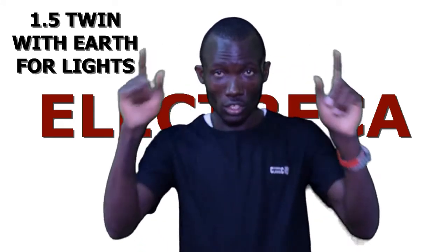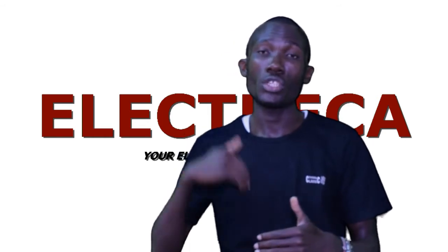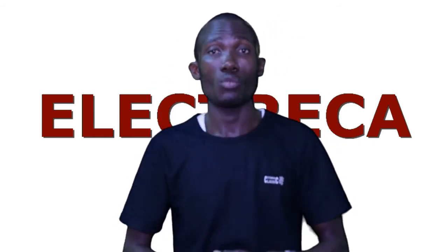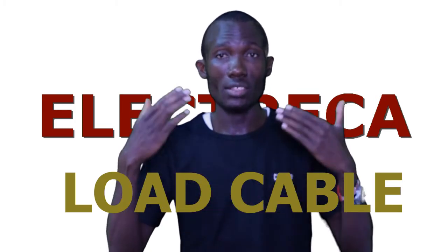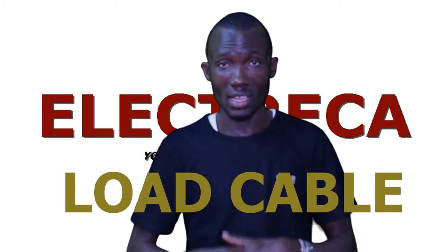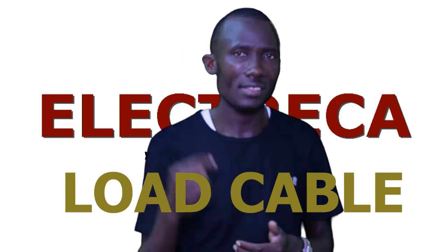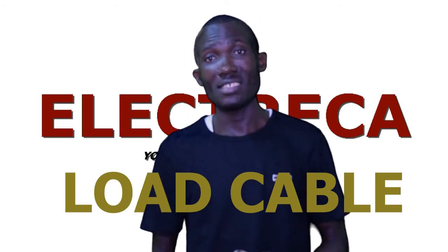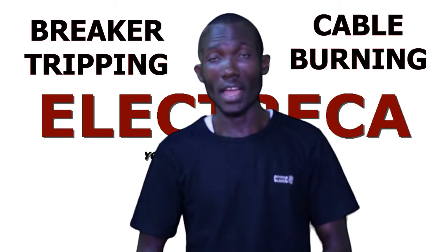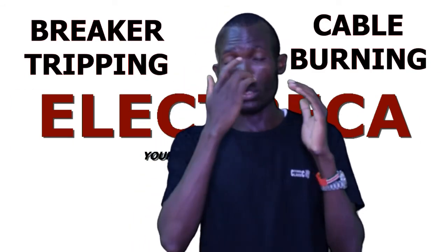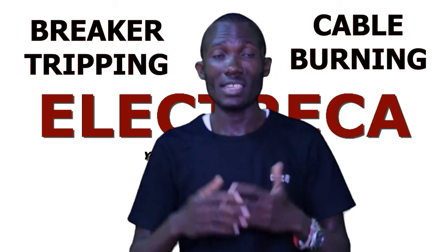But then after doing all those calculations, now you're going to come up with what we call the load cable. This load cable is the one that bears all the burden of those circuits, so you need to size it very carefully. If you undersize it, then you'll have problems of breaker tripping, cable burning, that kind of stuff. So your installer will use the information and then come up with a load cable.